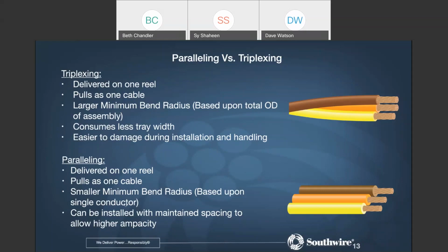What do I mean by that? Maintained spacing is where you keep the conductors separated from each other so that there's no mutual heating or very limited mutual heating of each other. And the NEC Article 392 on cable trays will allow you, depending on the type of cable tray that you have, to use a higher ampacity or higher current carrying capability for these conductors if you can keep them spaced out, separated from each other. So that's the maintained spacing. So with paralleling, if you want to have the conductors spaced out to try to allow for a higher ampacity, this is the way to do that, where it's delivered on one reel.